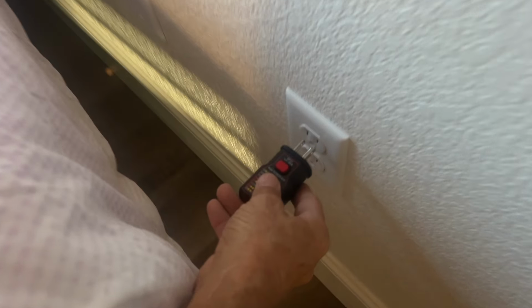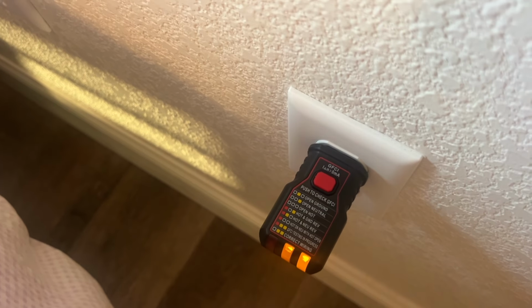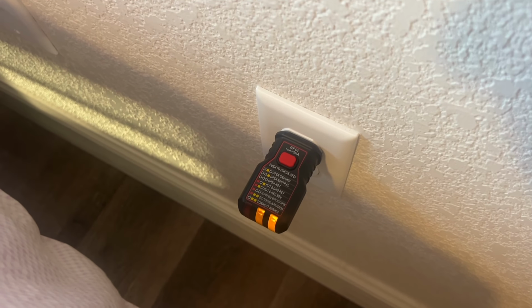We're going to plug it into one of the receptacles, go out to the breaker panel, figure out which breaker controls these receptacles, turn it off, then come back in and figure out which ones are dead so we know which ones are on the circuit. So I'm going to plug this in here, and then we'll go out to the breaker panel.